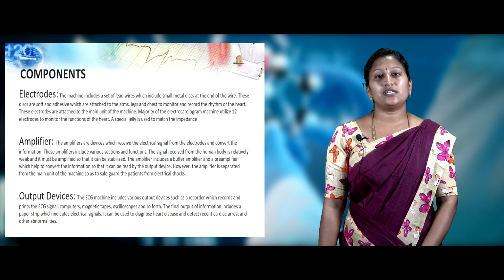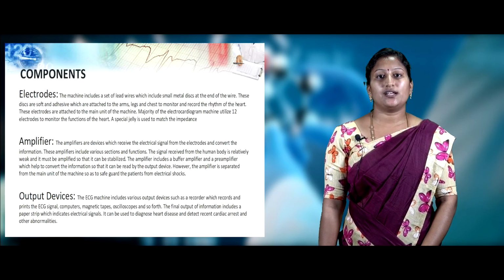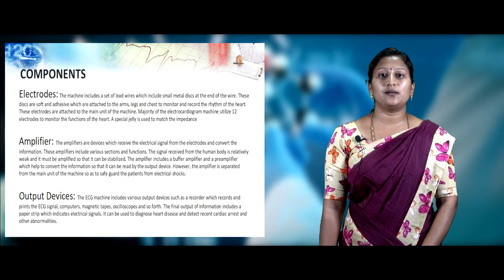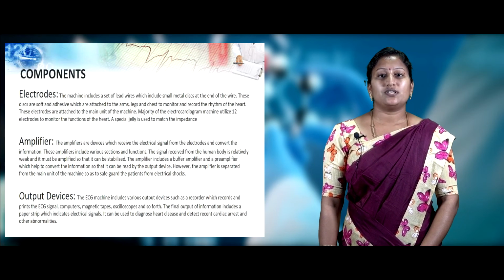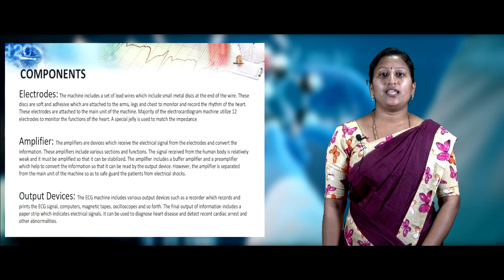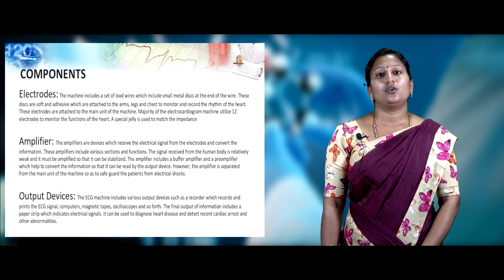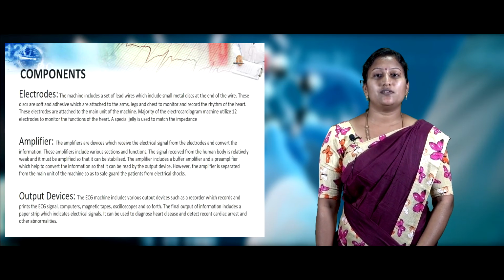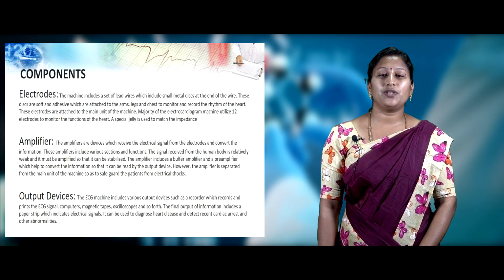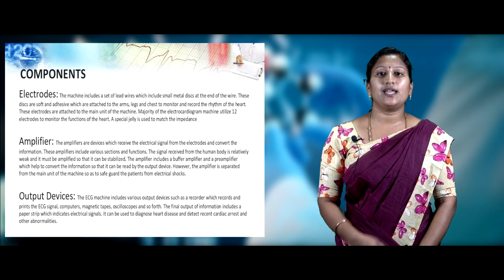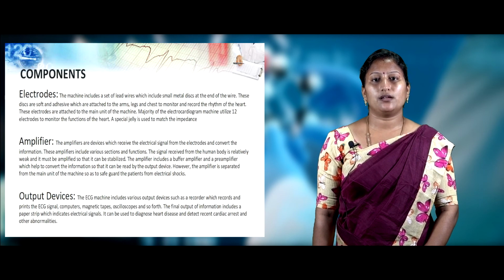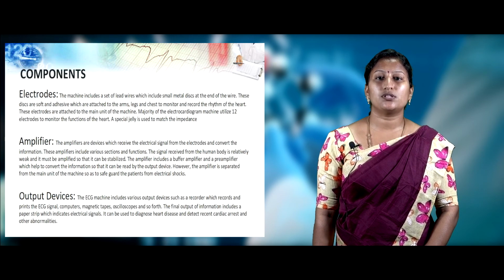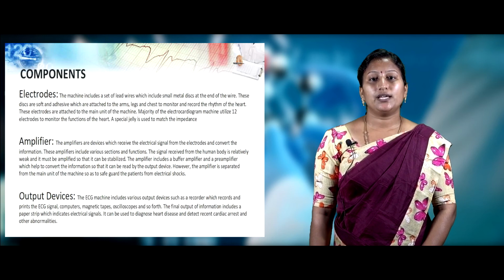The machine comprises a set of leads with metal discs at the end of the wires. These metal discs are soft and adhesive and can be placed on the surface of the arms, legs and chest. The majority of ECGs utilize 12 electrodes for the measurement of electrical activity of the heart. A special jelly is used to maintain the impedance difference. The amplifier is a device used to acquire the electrical activity from the electrodes and it then amplifies the signals. The amplifier includes a buffer amplifier and preamplifier in order to convert the information so that it can be read by the output devices. Different output devices like recorders, computers, magnetic tapes, oscilloscopes and so forth are available and can be chosen based on the requirement.